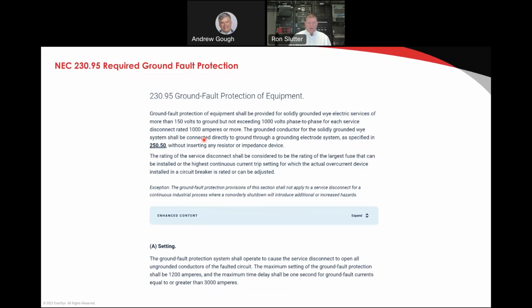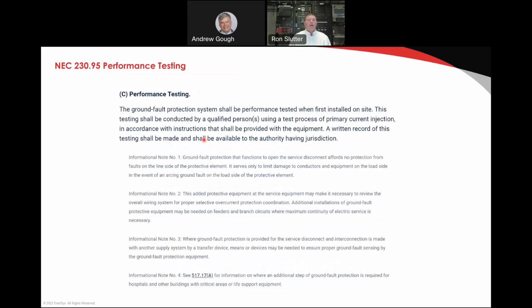And then when we ground fault equipment, we also have to provide performance testing when we use ground fault equipment, required by the code. These are new code sections that are often missed when upgrading facilities to new and larger capacity because we haven't seen that kind of capacity before. So people get used to doing things the same old way. And this is not the same old thing. When you upgrade beyond 1,000 amps, you really need to make sure that your design has been configured properly.